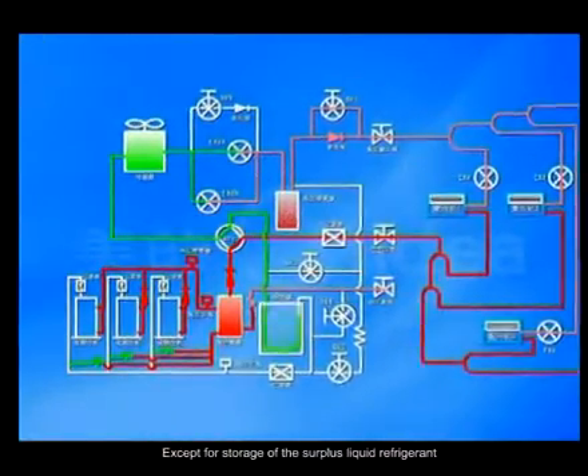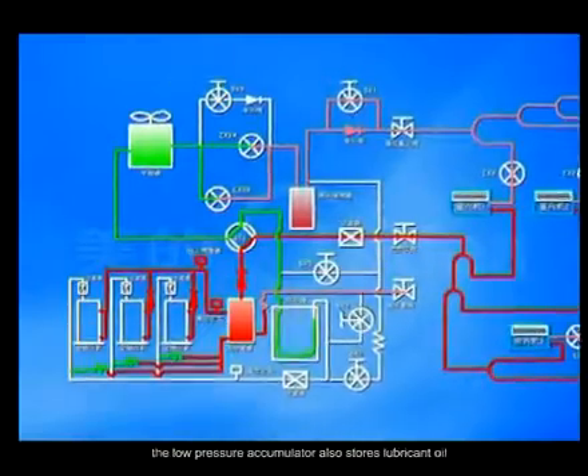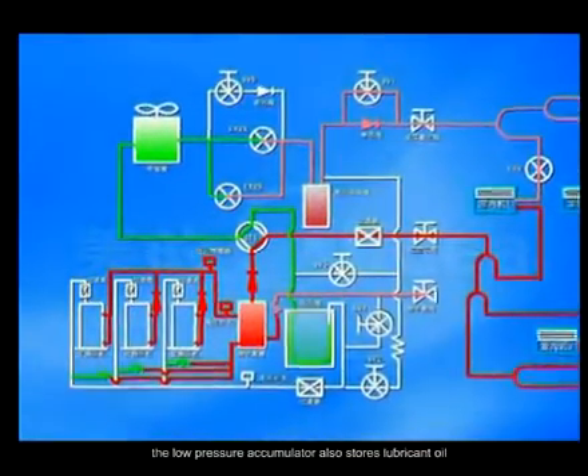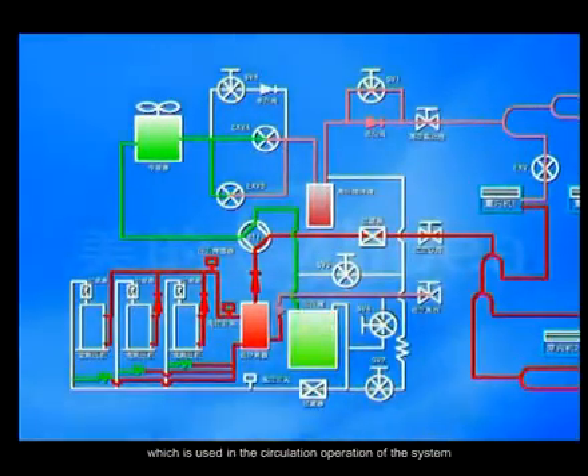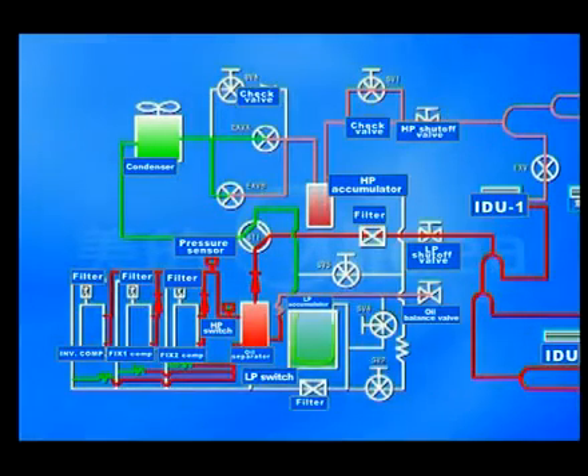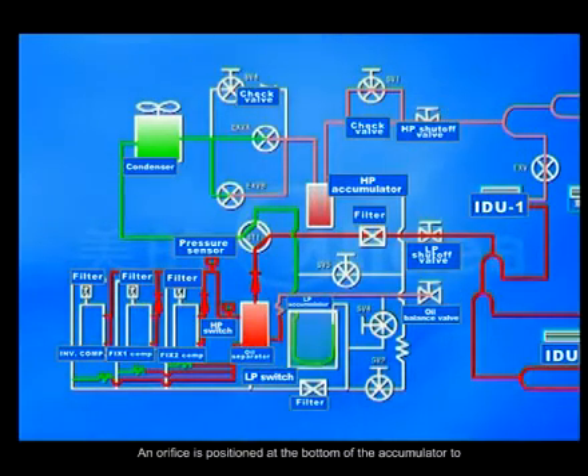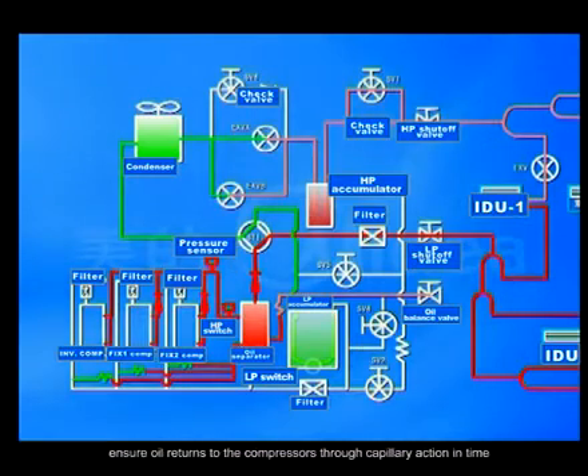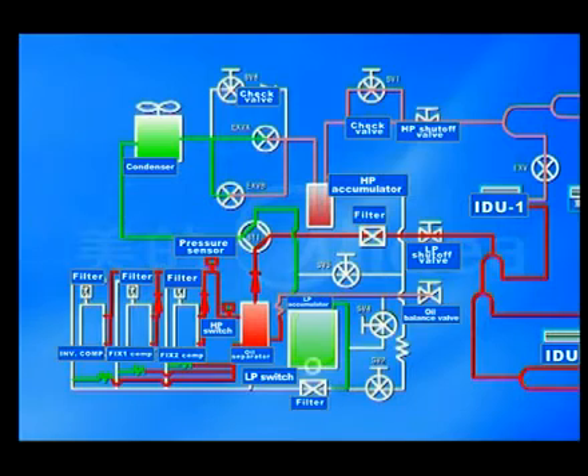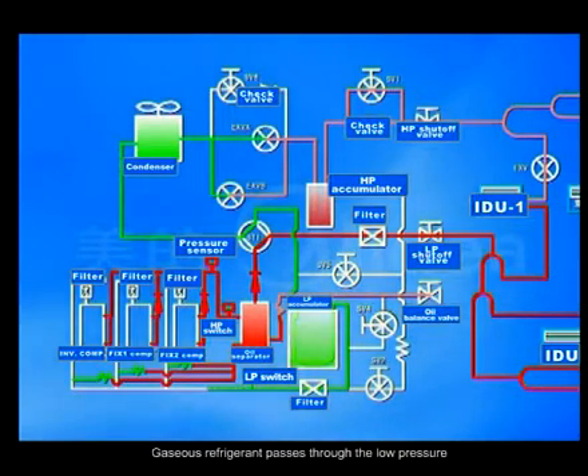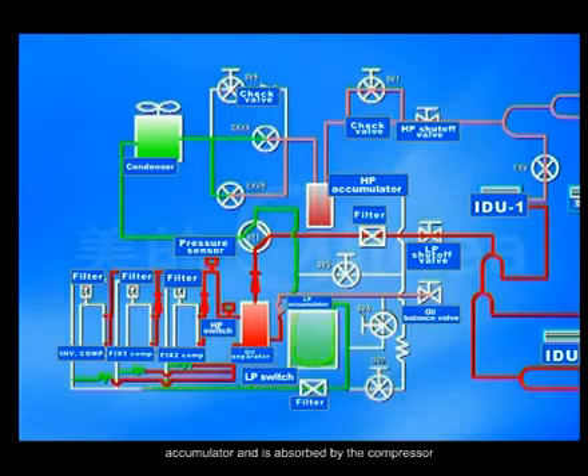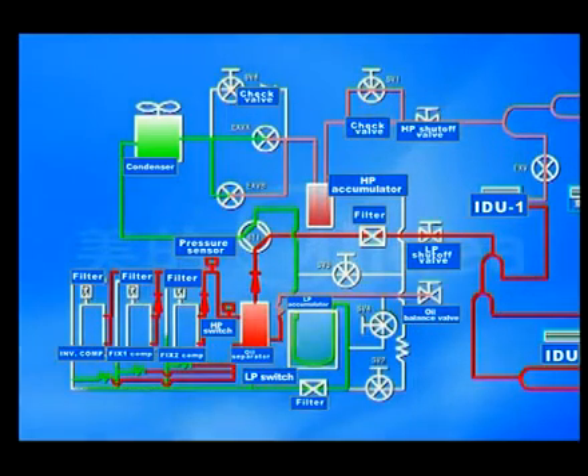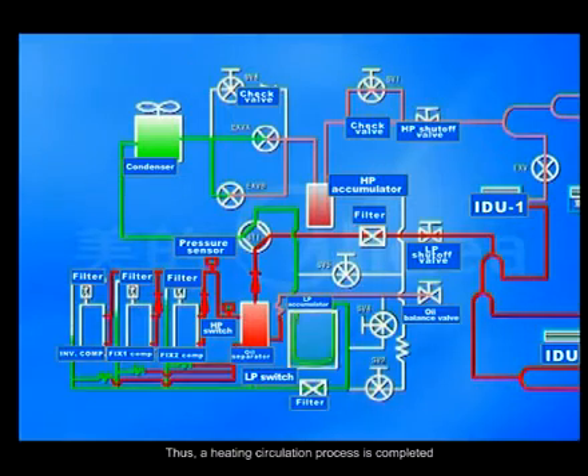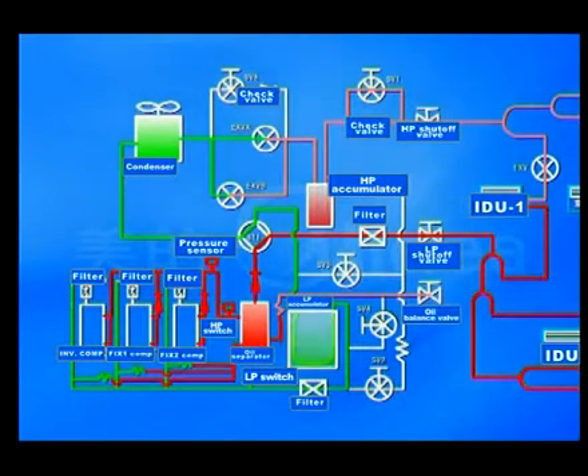This ensures that the refrigerant absorbed by each compressor is in the gaseous state. Except for storage of the surplus liquid refrigerant, the low-pressure accumulator also stores lubricant oil, which is used in the circulation operation of the system. An orifice is positioned at the bottom of the accumulator to ensure oil returns to the compressor through capillary action in time. Gaseous refrigerant passes through the low-pressure accumulator and is absorbed by the compressor. Thus, a heating circulation process is completed.